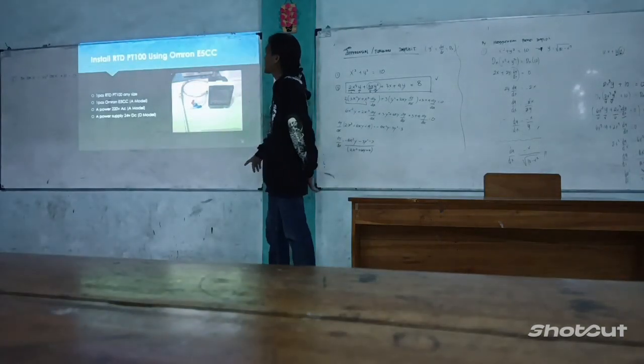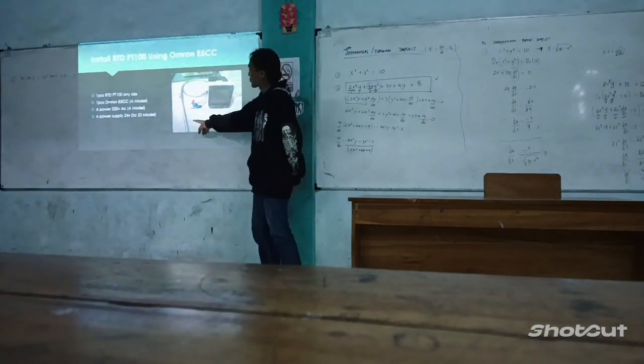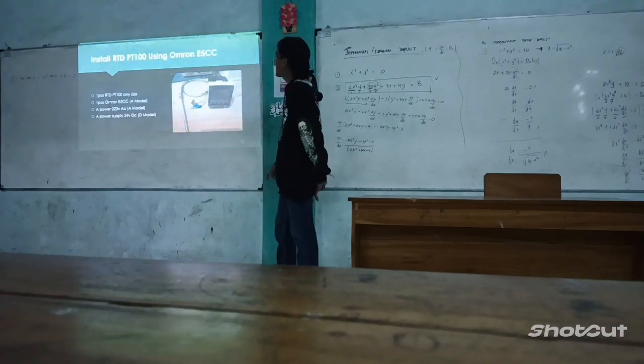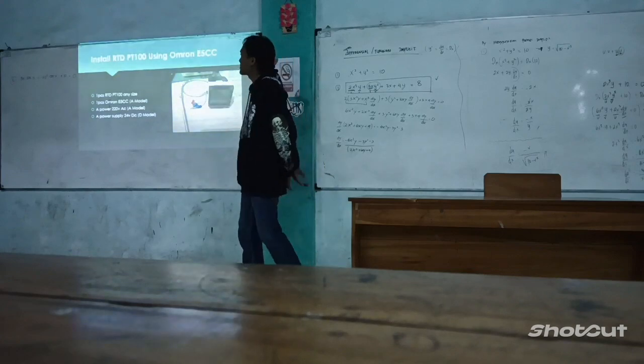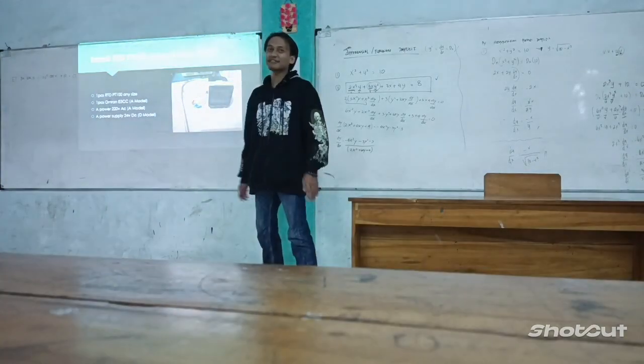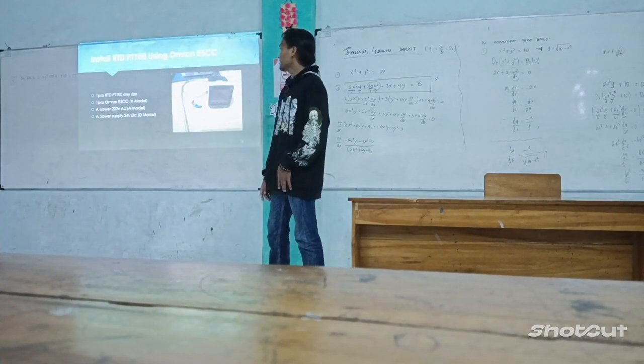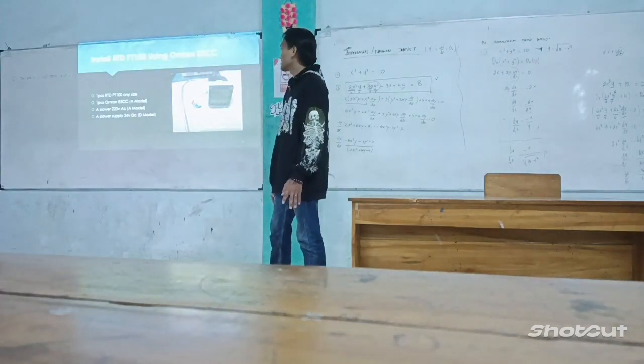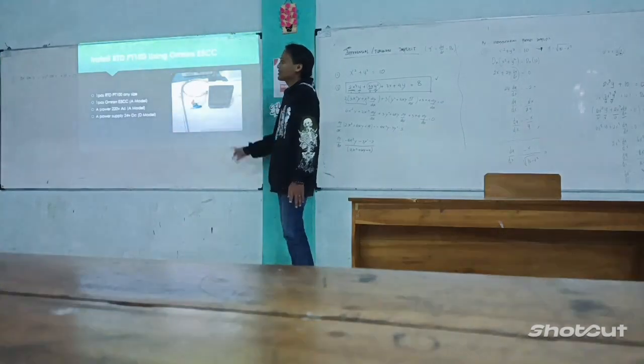And this is installing the RTD PT100 with the Omron E5CC as the display controller. First you need one piece of RTD PT100, any size, any type, and second, one piece of Omron E5CC A model.